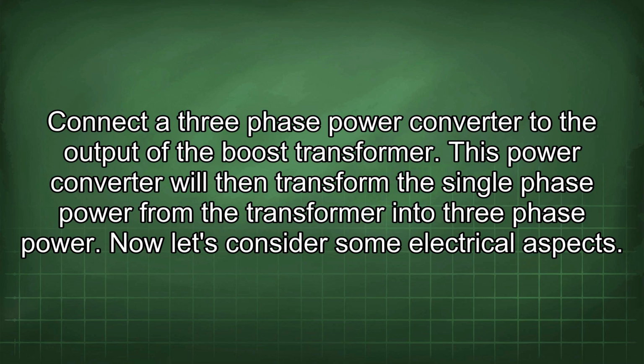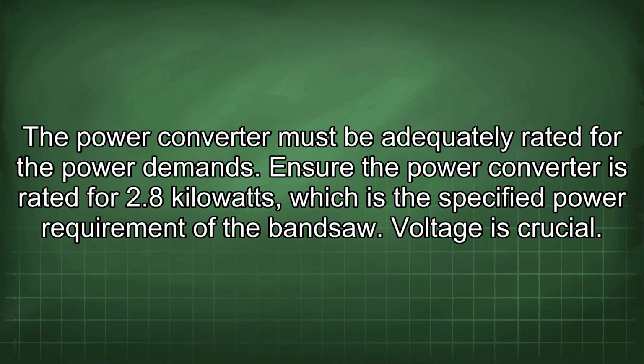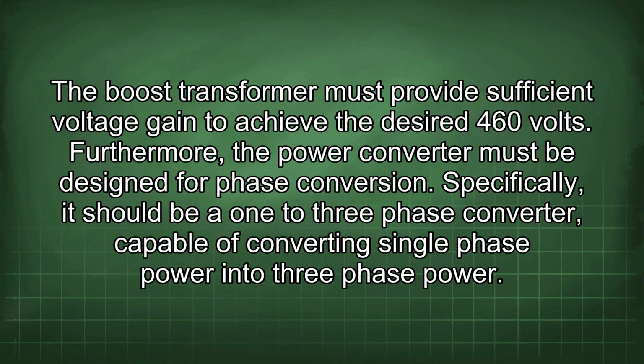Now let's consider some electrical aspects. The power converter must be adequately rated for the power demands. Ensure the power converter is rated for 2.8 kilowatts, which is the specified power requirement of the bandsaw. Voltage is crucial. The boost transformer must provide sufficient voltage gain to achieve the desired 460 volts. Furthermore, a power converter must be designed for phase conversion. Specifically, it should be a 1 to 3 phase converter, capable of converting single-phase power into three-phase power.